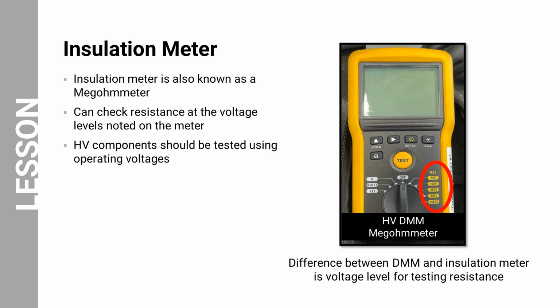While a DMM can measure resistance, its voltage output is typically limited to low ranges under 1,000 volts. This makes it unsuitable for testing high voltage components where leakage currents are of concern. On the other hand, an insulation meter provides the high voltage necessary to simulate operating conditions and effectively detect even minor insulation weaknesses that could lead to isolation faults. In essence, the high voltage capability of an insulation meter makes it the ideal tool for isolation fault testing, allowing technicians to identify potential safety hazards and ensure the integrity of the high voltage system.